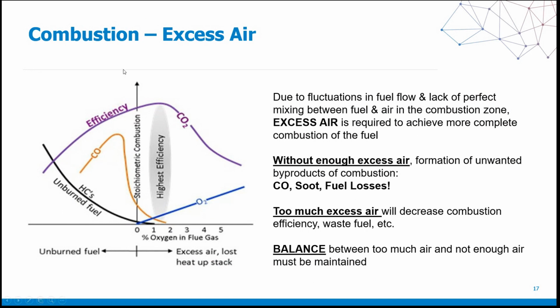Because if we look at this curve here, this gray shaded area on this graph, this is where the manufacturers want us to be. This is our 0 to 22 ppm of CO. This is our 3 to 9% oxygen, and this is our anywhere from 5 to 11% of CO2. So it's very, very important that we understand where we're at, because this is our air-rich side of the equation, and this is our fuel-rich side of this equation. We always want to be on the air-rich side.